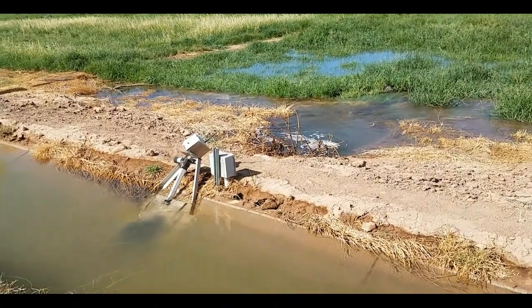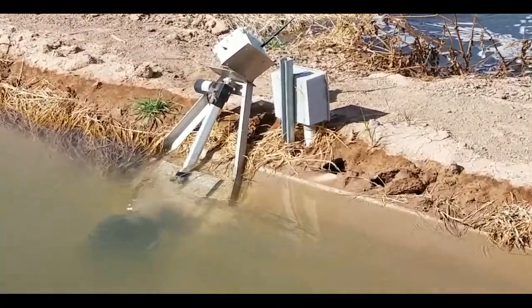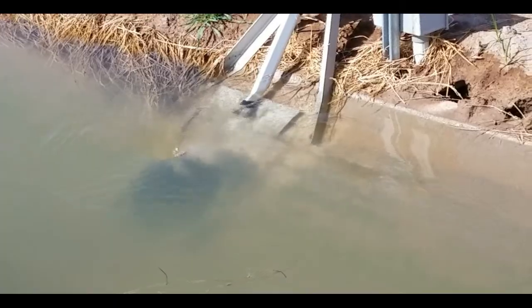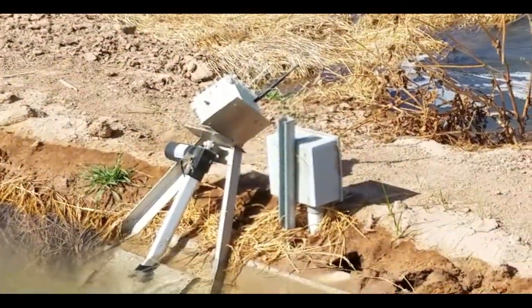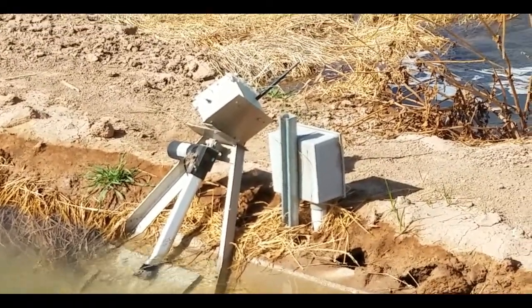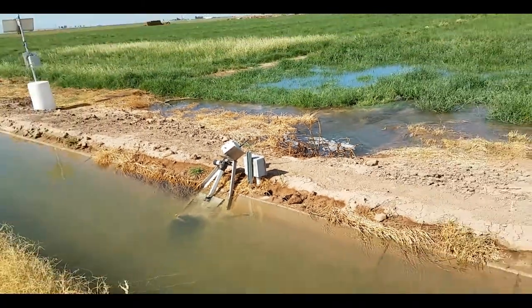Note irrigation flow passing through an open pipe gate. Water passes through the pipe, heading across the land towards the drainage ditch where excess flow is sent off-field. Halfway down the field is a water present sensor that alerts the hub that water has traveled that distance, so the hub can calculate its unique transit time for that day and predict the additional time necessary to complete the watering.